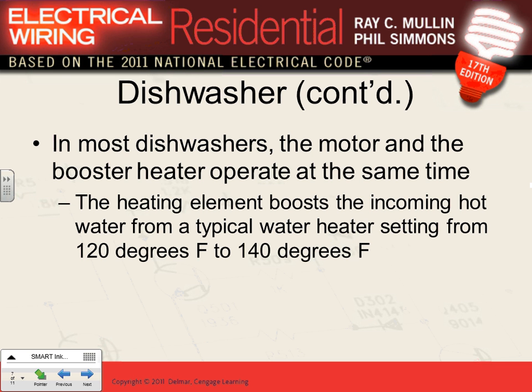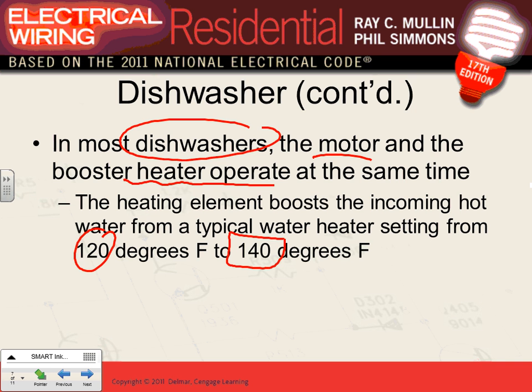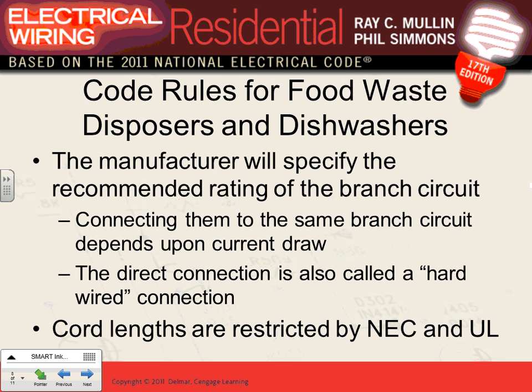A couple of other things, guys. Dishwashers and motors. The dishwasher, as you know, has a heater as well as a motor to rotate things. So these are an appliance. The manufacturer will come up with a nameplate amp rating for them because there's a heater and there's a motor, and we take that nameplate and apply the rules for it. A couple of things about the temperature. This is where they take the hot water and raise it up to 140-degree temperature so they can wash your dishes, but that's FYI only.